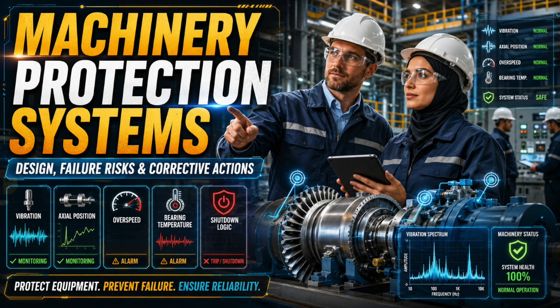Connectors must be protected. Instruments must remain accessible, and protection system components must not be hidden behind insulation, piping, covers, or poor layout. A system that cannot be accessed will eventually be bypassed. A system that is frequently noisy will eventually be distrusted. A system that is not documented will eventually be mismaintained.